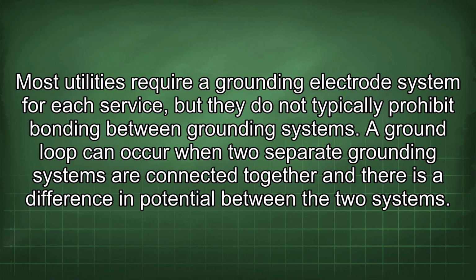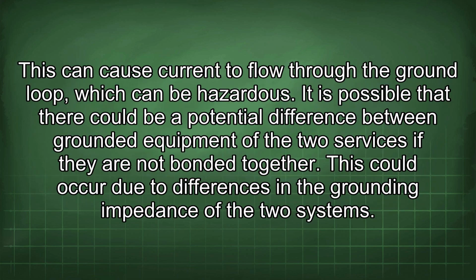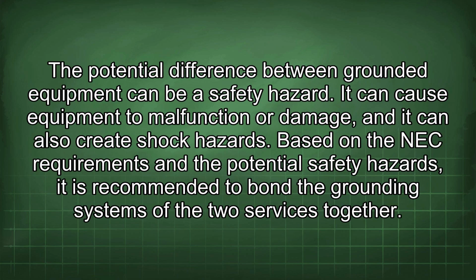A ground loop can occur when two separate grounding systems are connected together and there is a difference in potential between the two systems. This can cause current to flow through the ground loop, which can be hazardous. It is possible that there could be a potential difference between grounded equipment of the two services if they are not bonded together. This could occur due to differences in the grounding impedance of the two systems. The potential difference between grounded equipment can be a safety hazard. It can cause equipment to malfunction or damage, and it can also create shock hazards.